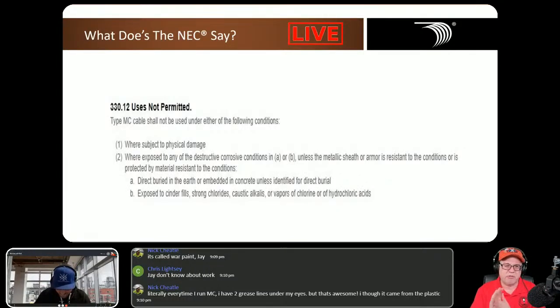Here's what the National Electrical Code says under 330.12, uses not permitted: type MC cable shall not be used under either of the following conditions. We have two conditions here. Number one, we already know it can't be used where subject to physical damage.